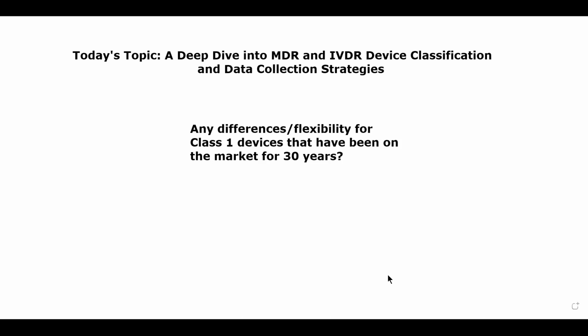Differences for class 1 devices: the key differences are that several of them have been reclassified up to class 2A or 2B. And then there are 4 different designations under class 1, like subdivisions, subsets of the classification. So you've got the sterile classification, the measuring, the reusable, and then the general class 1 devices. Those are new distinctions that the MDR calls out, and for each of those they have different sub requirements. They're not hugely burdensome, but they're something to address in your CER. You need to reclassify your device if any of those categories apply. So those are some of the key differences.